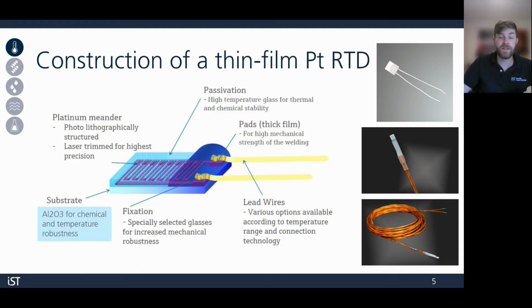At the end, the sensors are measured and sorted into the different accuracy classes. So you might be familiar with IEC 60751 class A, B, AA. If you want to learn more about those, we have a temperature webinar on our YouTube channel, which goes through those. So the operating principle of these RTDs is pretty straightforward. As temperature increases, the resistance also increases. And these can be customized in a number of different ways, but today we'll focus on wire customization, in particular 2- and 4-wire cable extensions.